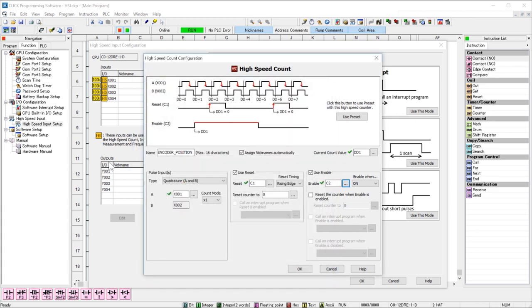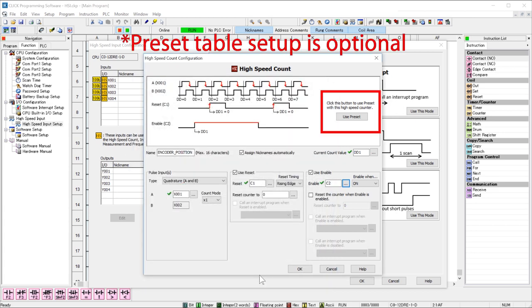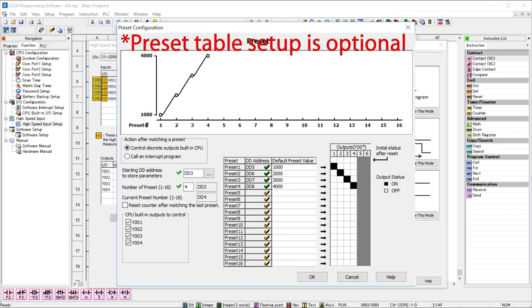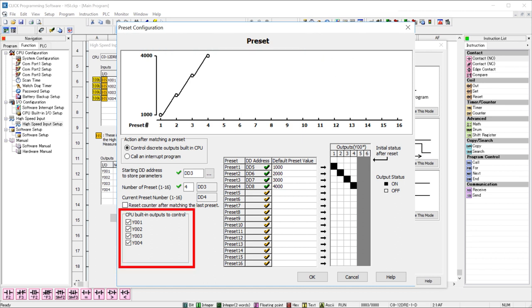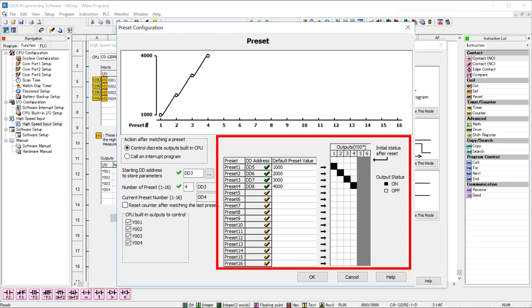Now, there is another feature here that you might find useful. You can define a preset table that will turn on outputs or call an interrupt program when the encoder count reaches a certain value. This is completely independent of the scan time and can be very useful in certain high-speed operations.